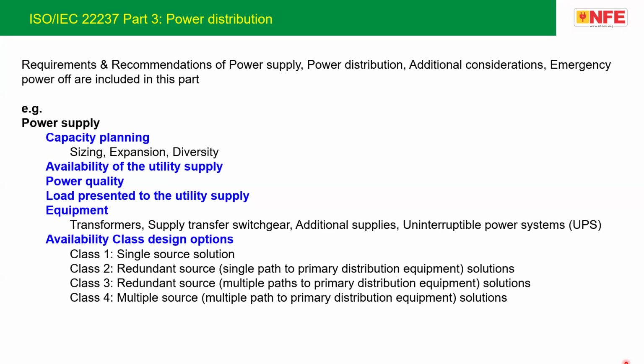With respect to diversity, availability classes 3 and 4 ask for duplication and diverse routing of the incoming power supply. That means there should be two paths from the main grid, and they should not mix with each other. Now, regarding the availability of utility supply, we should cross-check this with the utility during due diligence. It is actually the reliability, whether the backend system of the transmission power supply is reliable or not. For that, we can check the capacity of that grid, period of use, and the load profile also.